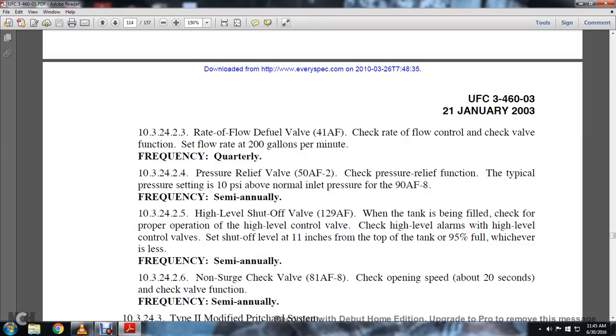High level shutoff valve, the 129 AF: when the tank is being filled, check the proper operation of the high level control valve. Check the high level alarms and high level control valves. Set the shutoff level at 11 inches from the top of the tank or 95% full, whichever is less. The frequency for a high-level shutoff valve inspection is semi-annually. Non-surge check valve: check the opening speed, about 20 seconds, and check the valve function. That is done semi-annually.